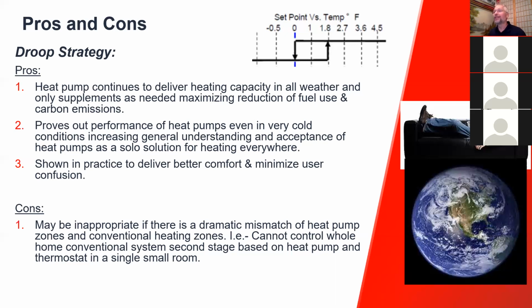Okay, so the con, as I've mentioned already a couple of times, is if you have a dramatic mismatch in the zones between the ductless distribution and the conventional zones, droop is not going to do a particularly good job without having some separately controlled zones. And that could be like, if people didn't have a well-insulated or well air-sealed basement, and they didn't have a heat pump in the basement, and they previously had a boiler down there keeping it warm, and they were concerned about the basement freezing or something along those lines.